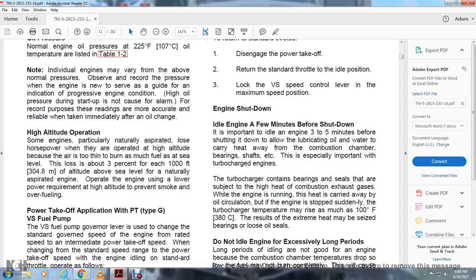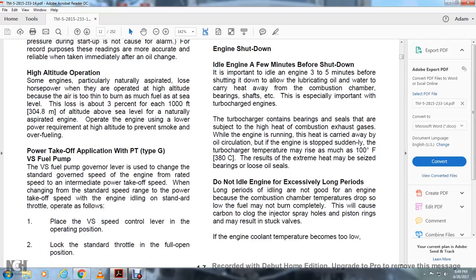Engine shutdown. Idle the engine a few minutes before shutting down. It's important to idle the engine 3 to 5 minutes before shutting down, allowing the lubricating oil and water to carry heat away from the combustion chamber, the bearings and shaft, etc. This is especially important with the turbocharged engine. The turbocharger contains bearings and seals that are subject to high heat from the combustion exhaust gas. While the engine is running, the heat is carried away by the oil circulation, but if the engine stops suddenly, the turbocharger temperature may rise as much as 100 degrees Fahrenheit. This may result in extremely high heat, seized bearings and loosened oil seals.